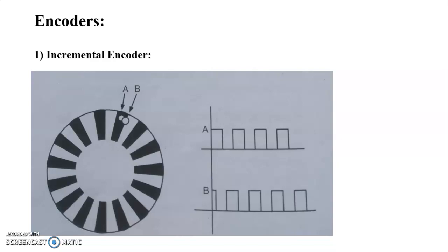The principle of the incremental measuring system is the scanning of a line pattern on the disk as shown in the figure. The states of the line pattern, transparent or not transparent, are converted into electronic pulses by an optoelectronic unit. The analysis of the signal is performed in an evaluation unit by counting up or down with each pulse. The current count is stored in digital form and is instantly available for evaluation.